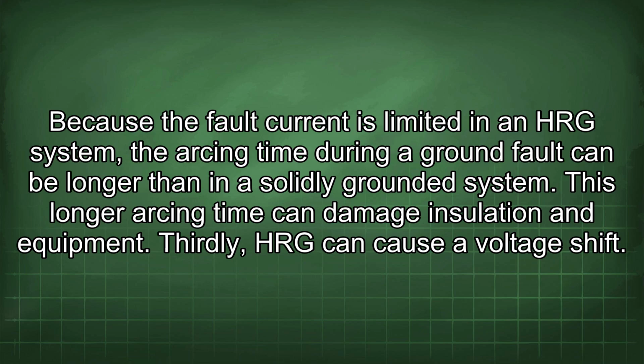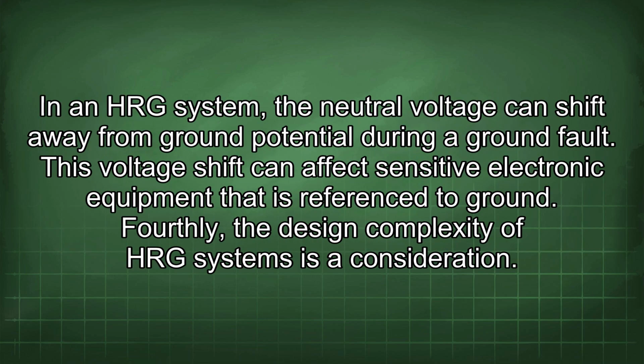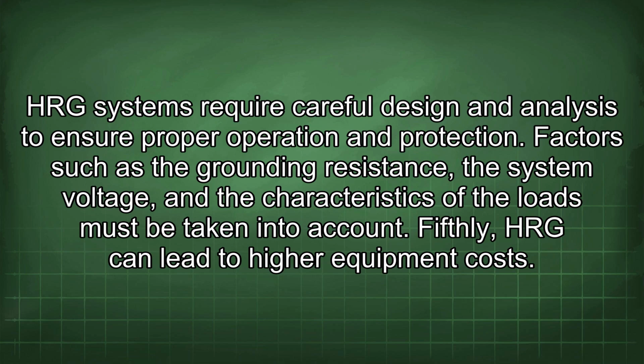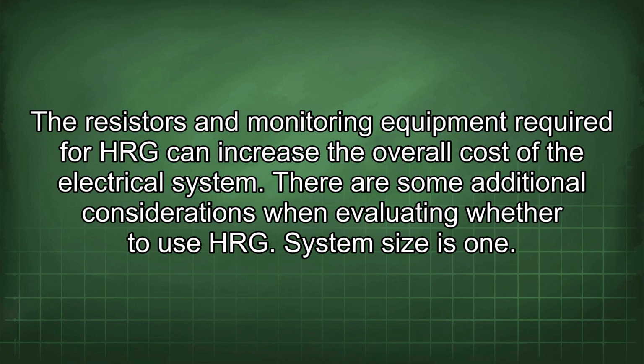Thirdly, HRG can cause a voltage shift. In an HRG system, the neutral voltage can shift away from ground potential during a ground fault. This voltage shift can affect sensitive electronic equipment that is referenced to ground. Fourthly, the design complexity of HRG systems is a consideration. HRG systems require careful design and analysis to ensure proper operation and protection. Factors such as the grounding resistance, the system voltage, and the characteristics of the loads must be taken into account. Fifthly, HRG can lead to higher equipment costs. The resistors and monitoring equipment required for HRG can increase the overall cost of the electrical system.